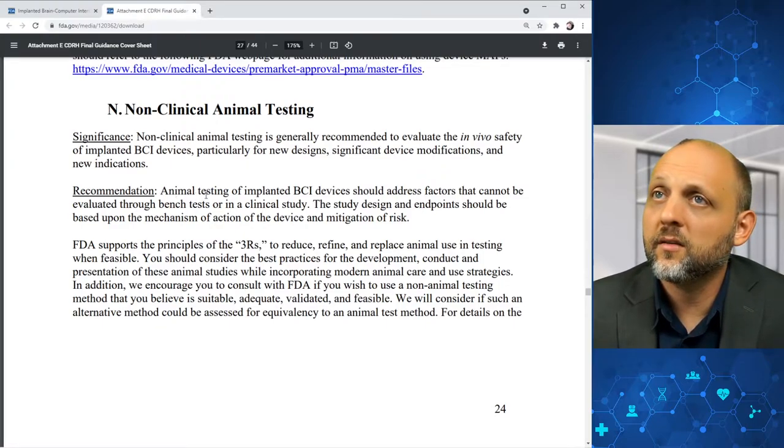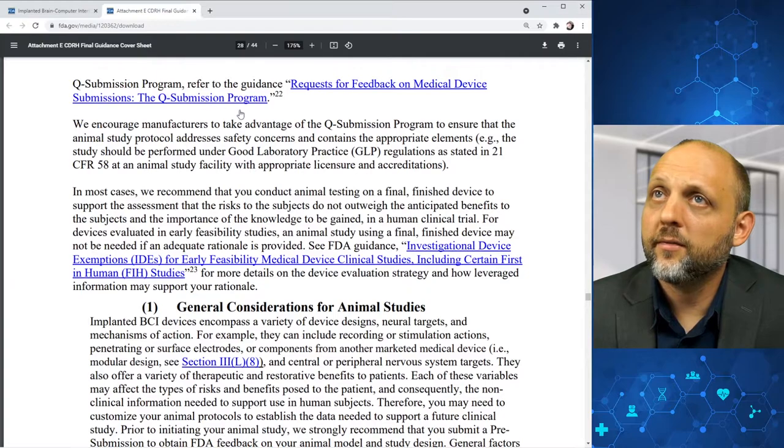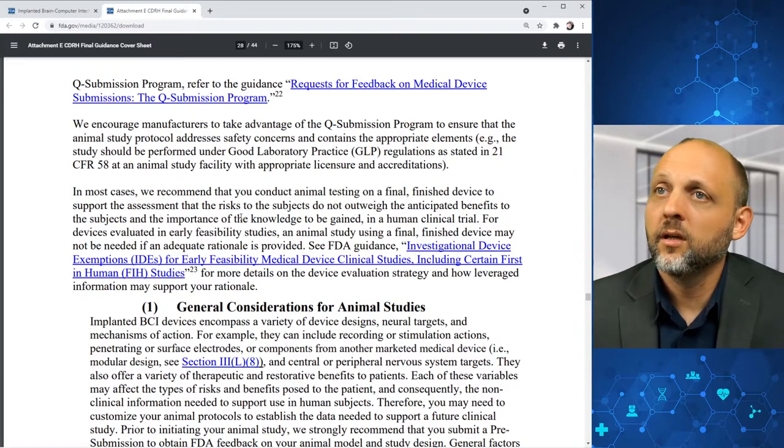And FDA says that animal testing of implanted BCI devices should address risk factors that cannot be evaluated through bench tests or in a clinical study. The study design and endpoint should be based upon the mechanism of action of the device and mitigation of risk.